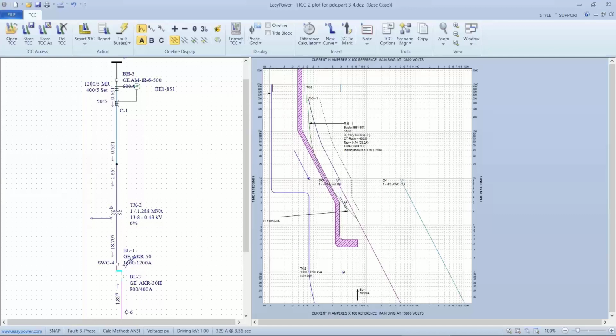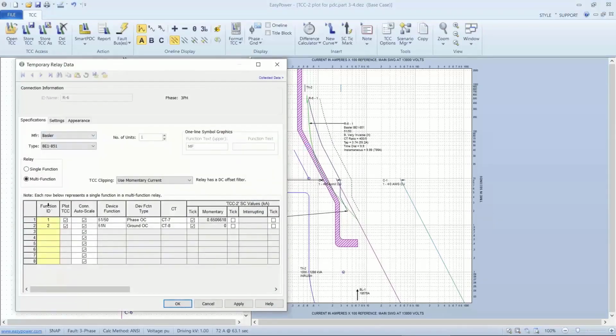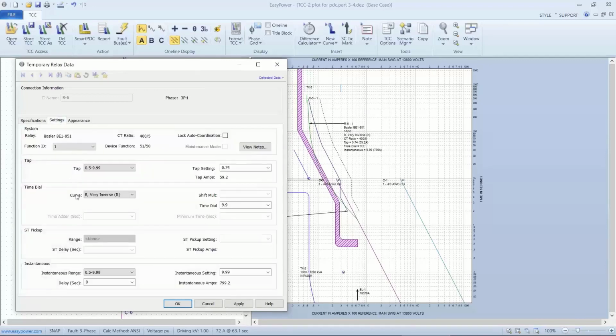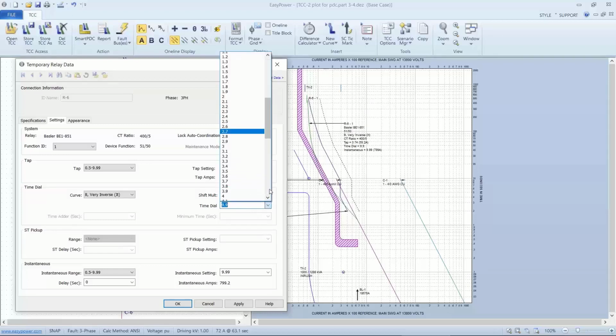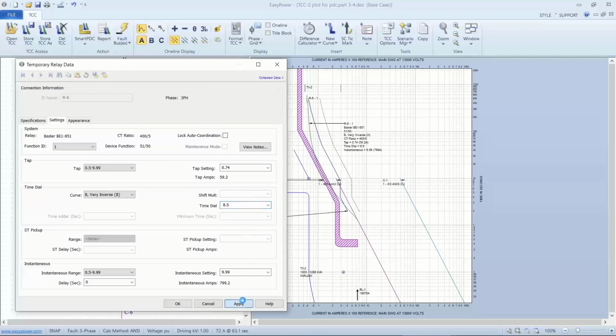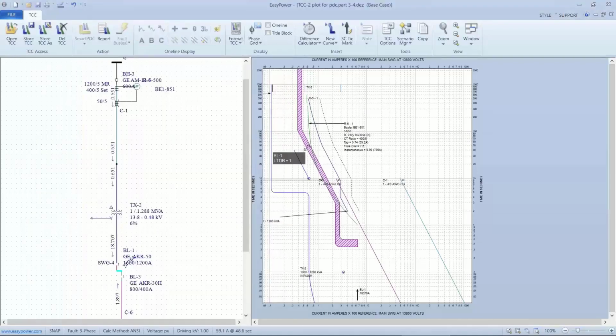Again, pulling it around on the screen gives me a limited amount of granularity. I might be better off doing this. Now, one thing that I didn't mention as we went through this, I'm on set point 1. There's an instantaneous setting with this relay. And so, Jim, I thought you said there shouldn't be an instantaneous setting except at the very first device. Okay, so I'm going to set my dial slower. I'll talk about the instantaneous in just a moment.